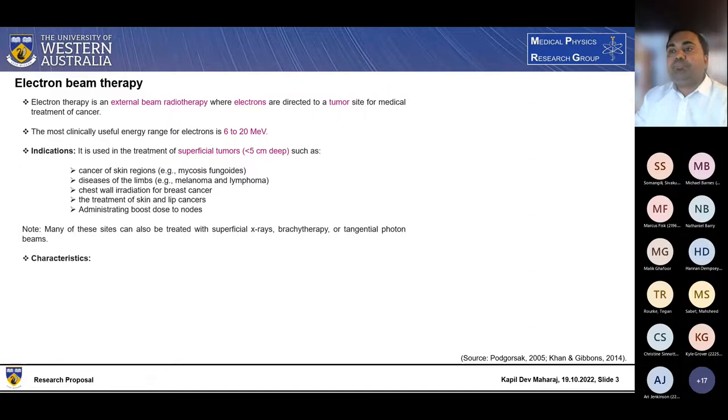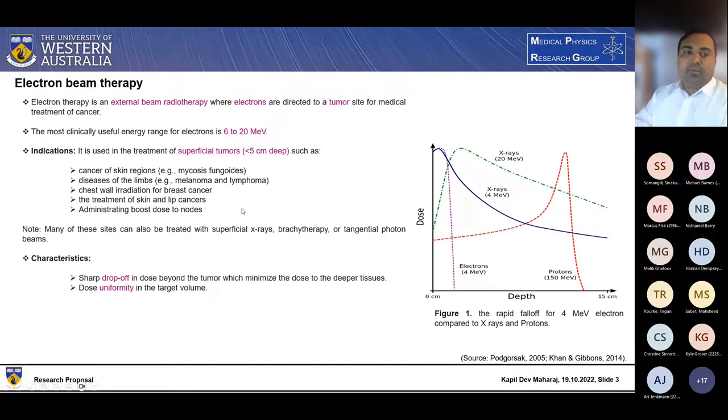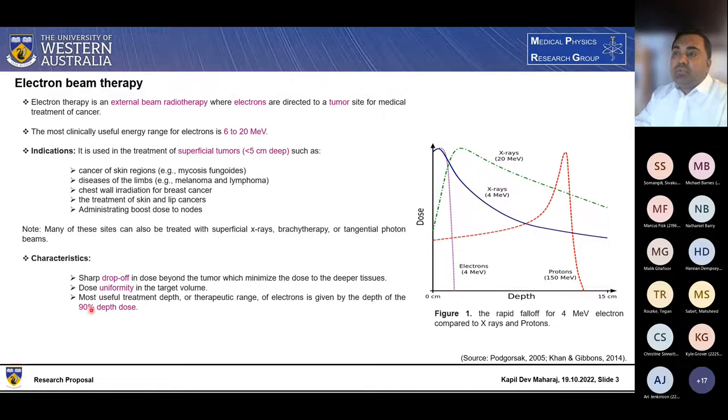So in terms of the key characteristics, the electron beam shows sharp drop-off beyond the tumor, which minimizes the dose to the deepest tissues, shows uniformity in the target volume. So as you can see in the picture on the left hand side, the curve in the green and blue show the percentage depth dose of the photons, which decreases with the depth gradually. However, if you see on the purple curve, which is the percentage depth dose of electron, which drops off very sharply. And another characteristic of the electron beam is the most useful treatment depth, which we use is the 90% depth dose. And it shows a bone sparing effect. So in comparison to the photon beam, it gives less dose to the bone.